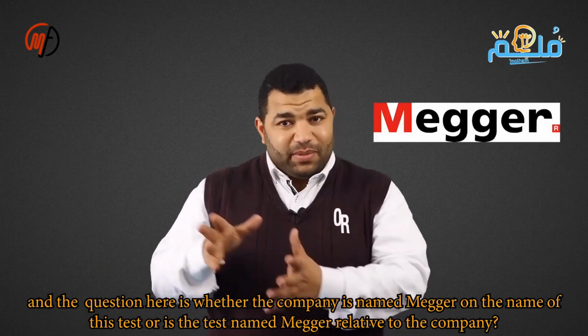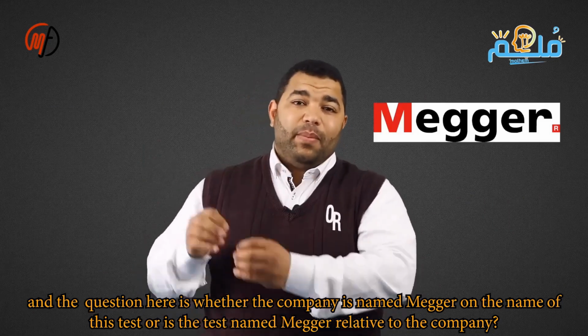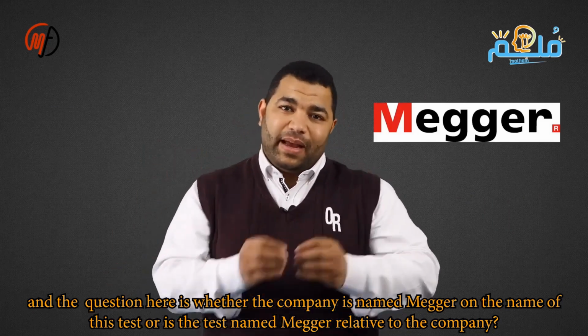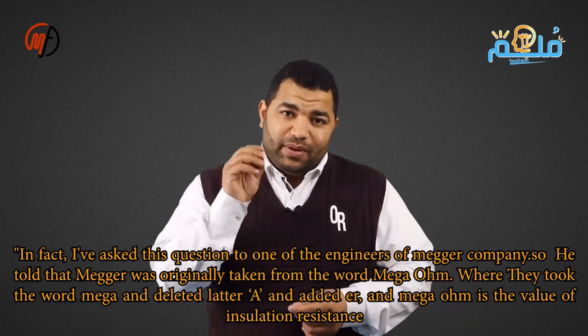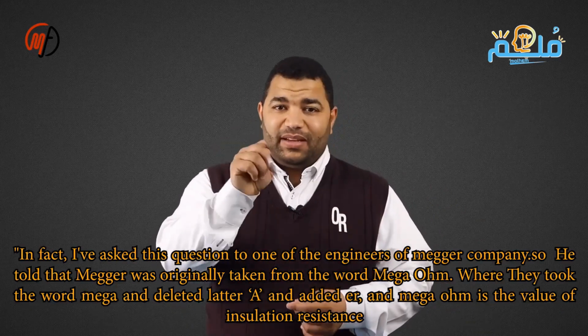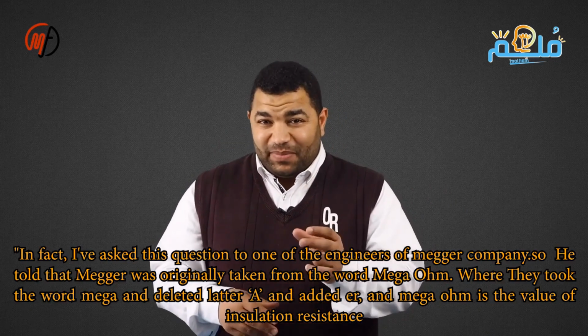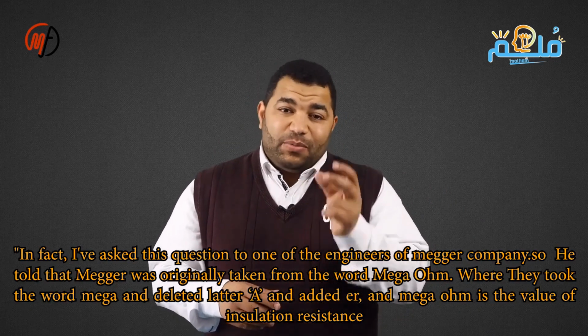A Megger engineer explained that Megger comes from mega ohm. They took mega, removed the A, and added er. The IR test is essential for electrical equipment. It's done for VT, CT, circuit breakers, bus bars, generators, and motors. It measures insulation resistance, ideally high to prevent leakage current.